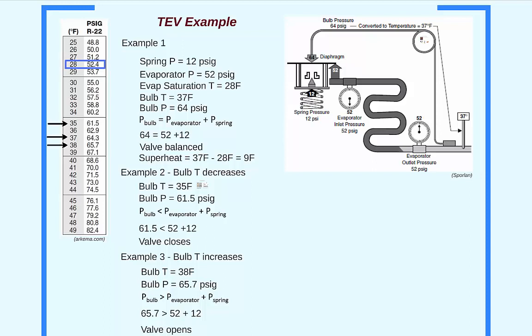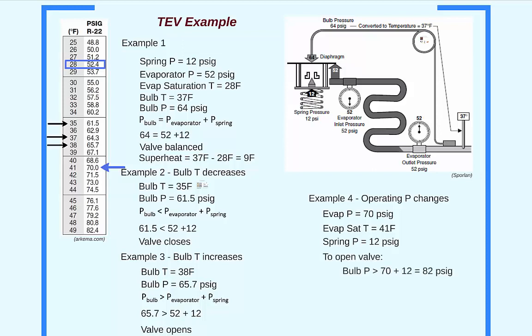Now, I mentioned before, the evaporator operating pressure depends on a number of factors and is not constant. What happens if the cycle operates at a different pressure? Let's look at an extreme case when the evaporator pressure rises to 70 psi. From the table, an operating pressure of 70 psi corresponds to a saturation temperature in the evaporator of 41 degrees. The pressures opening the valve are now 70 psi from the evaporator and 12 psi from the spring. A bulb pressure greater than 82 psi is required in order to open the valve. The sensing bulb will exert an 82 psi opening force when the sensing bulb temperature reaches 49 degrees Fahrenheit.